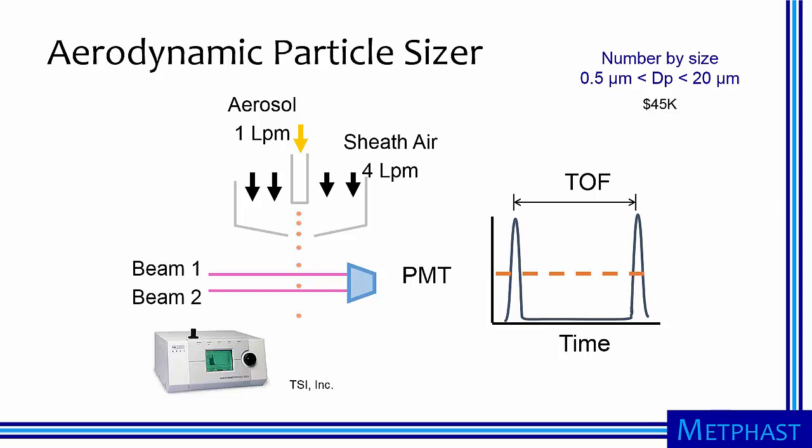An aerodynamic particle sizer uses the principle of inertia to size particles. An aerosol is rapidly accelerated through two laser beams. A photomultiplier tube is used to measure the light scattered by the particle as it passes through the beams, creating two light pulses.